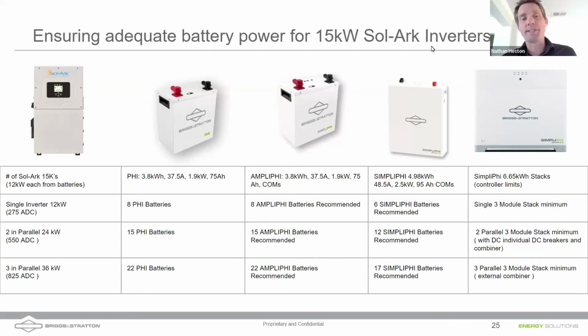I'm going to mention here just briefly on sizing. If you are sizing this and you're using one of our communicating batteries, but you don't have enough batteries on your system, there are power output limitations to batteries. Our previous batteries were all rated at C/2. I mentioned the ability of a single 6.6 battery to discharge at 1 C, which is in 1 hour. So batteries have power limitations in addition to capacity limitations. Everybody thinks of the battery and how much overall capacity it has, how much energy is there, but there are also power output limitations. So if you're using one of the smaller communicating batteries, but you only have, let's say, 4 batteries for a 15K, the limitations on those battery outputs are probably going to limit your overall power that you can pull from the DC bus, which would limit the amount of power that Sol-Ark is going to be able to output.